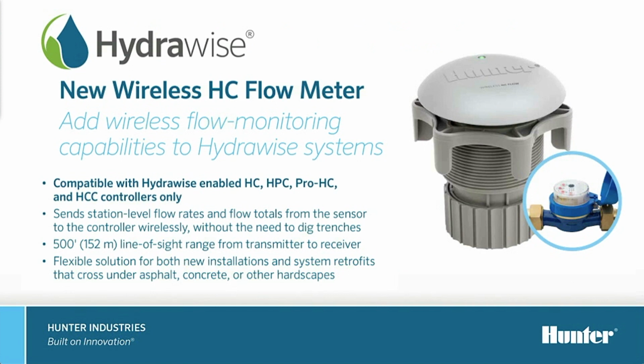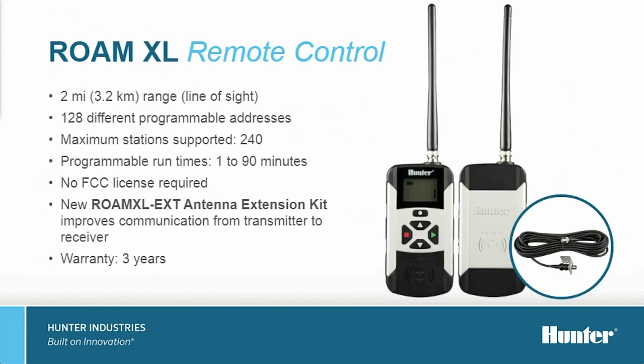Hydrawise has also added a new wireless flow sensor option, which is a great way to retrofit flow monitoring and flow alarm monitoring to an existing system that may not have had a flow sensor in the first place. It is compatible with virtually all the Hydrawise controllers, and it has up to 500 feet, 150 meter line of sight range, license free, from the transmitter, wherever the flow sensor is, to the receiver back at the controller location. So it allows easy retrofit without cutting, patching, and trenching to add flow monitoring to an existing installation.